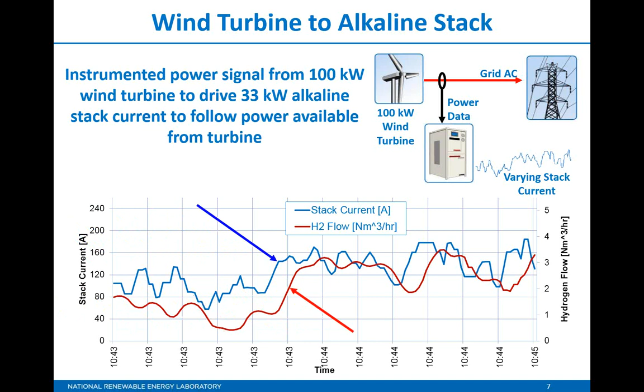This slide shows that, in this case, the alkaline electrolyzer, which has a 33 kilowatt stack inside, can follow a varying signal from wind. I call this the classical approach: you read the power the wind turbine's putting out, take power data from that, and vary the control signal you provide to the power supply that sends current to the stack. The blue line represents stack current, and the red is the output hydrogen flow from the system. So it's a pretty basic way to set up your system and operate it in conjunction with varying wind or solar.